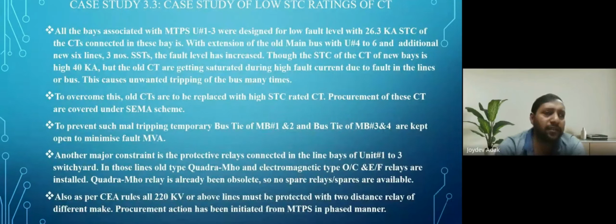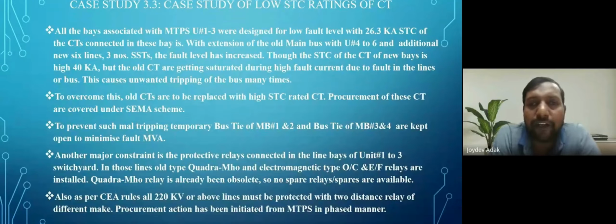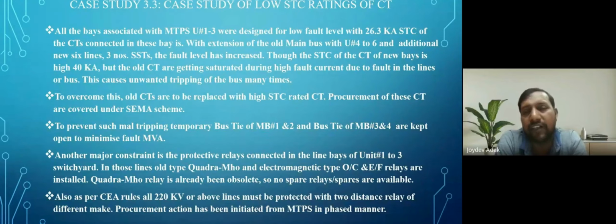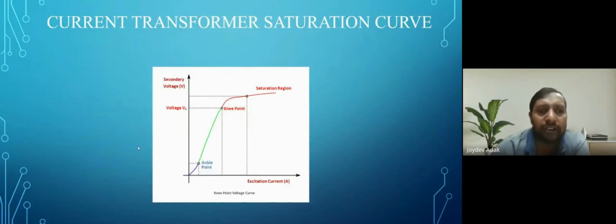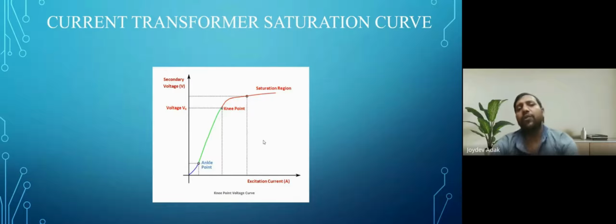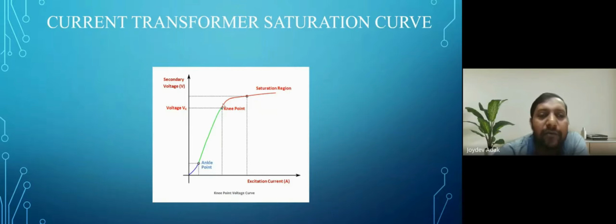Another case study is the short circuit rating of current transformers. For a major thermal power station, the 220 kV CTs have a 26.3 kiloampere short circuit rating. For CT measurement, there are two types: protection CT and metering CT. This is the excitation curve. For protection CT, the saturation is in the higher zone, and for metering CT, the saturation level is at the level of full load current, so that it cannot damage any meter. And for protection CT, this straight line is the main point.